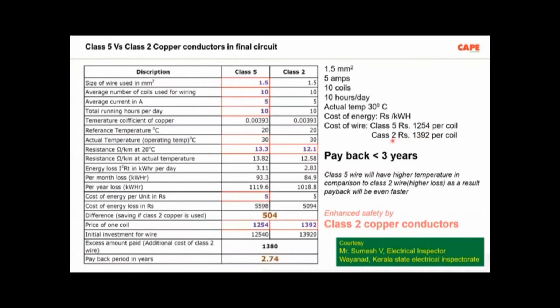Class 2 copper. The difference is the wires are thicker, the strands are thicker. As a result, maybe a little bit more copper has to be used. I'm not aware of such things; that is the job of the wire companies. Anyway, for a safety engineer, what is important is the offered resistance of that particular wire. Class 2 wire has a lesser resistance, but a higher cost.